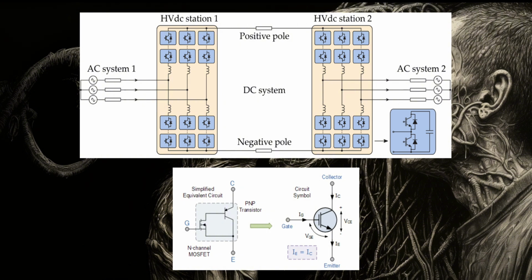The converters operate at a high frequency with pulse width modulation, PWM, which allows simultaneous adjustment of the amplitude and phase angle of the converter while keeping the voltage constant. VSC technology has a high degree of flexibility with inbuilt capability to control both its active and reactive power. VSC HVDC has more technical advantages than the contemporary LCC HVDC, being a newer method of HVDC transmission technology.